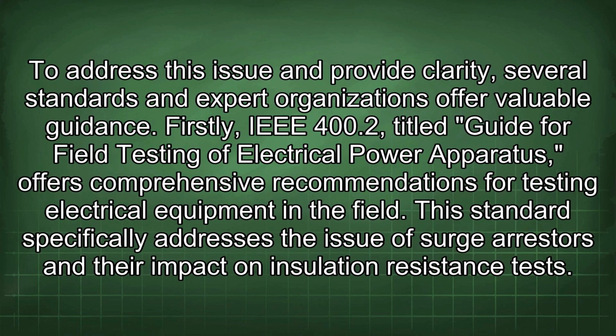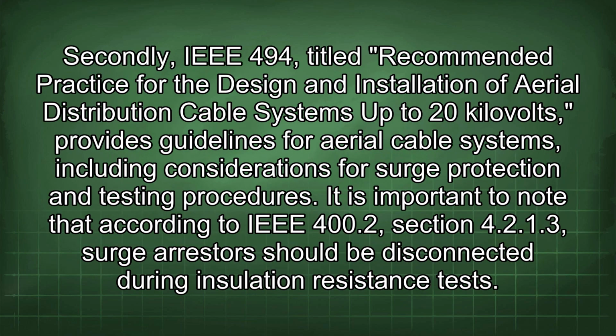To address this issue and provide clarity, several standards and expert organizations offer valuable guidance. Firstly, IEEE 400.2, titled Guide for Field Testing of Electrical Power Apparatus, offers comprehensive recommendations for testing electrical equipment in the field. This standard specifically addresses the issue of surge arrestors and their impact on insulation resistance tests. Secondly, IEEE 494, titled Recommended Practice for the Design and Installation of Aerial Distribution Cable Systems up to 20 kV, provides guidelines for aerial cable systems, including considerations for surge protection and testing procedures.